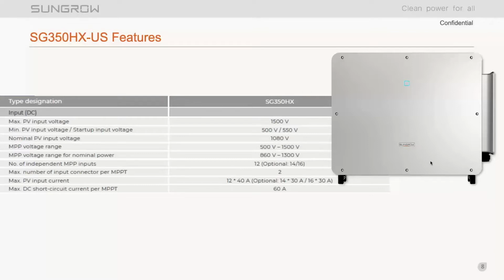And then with that, the max PV input current is going to be 40 amps per power point tracker with the 12 MPPT option, and then 30 amps per MPPT with the optional 14 or 16 inputs. So that brings our max DC short circuit current per power point tracker to 60 amps, as opposed to the 50 amps that we realized with the SG250.